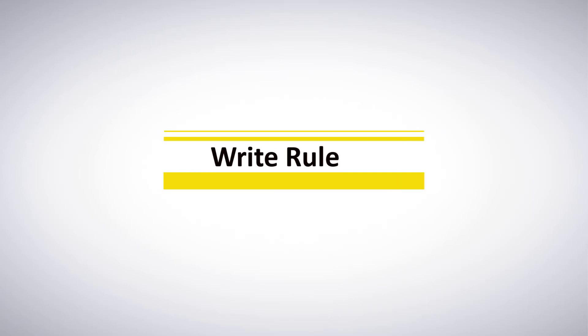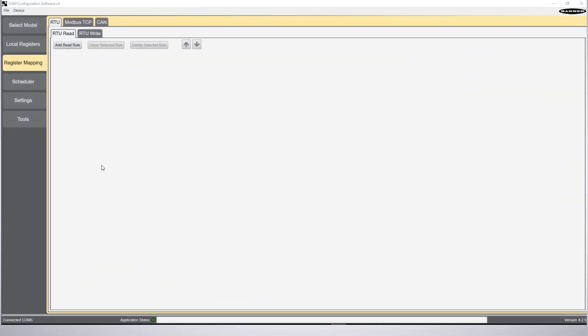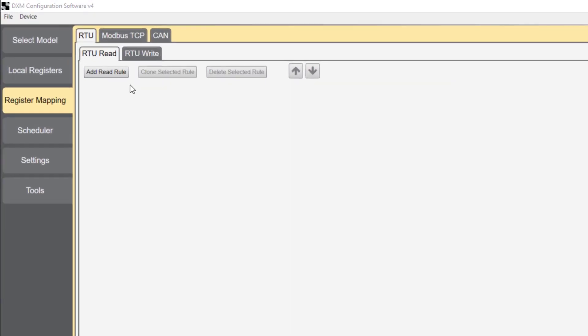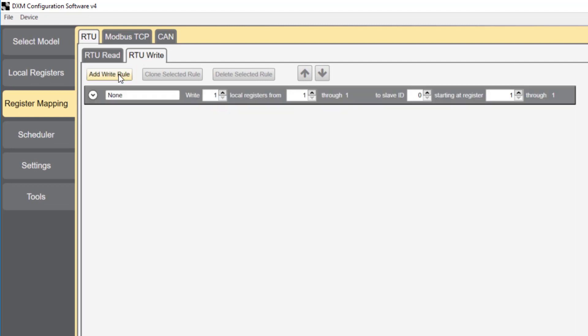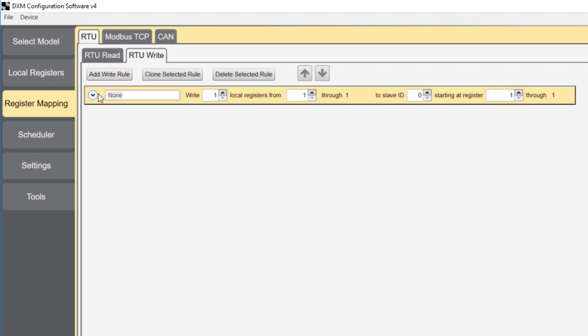This brings us to the write rule, which is under register mapping and RTU. Click RTU write, then add write rule. I'm going to name this node 1 output 1 red. It'll turn on when local register 1 goes high, which is the same as node 1 input 1.